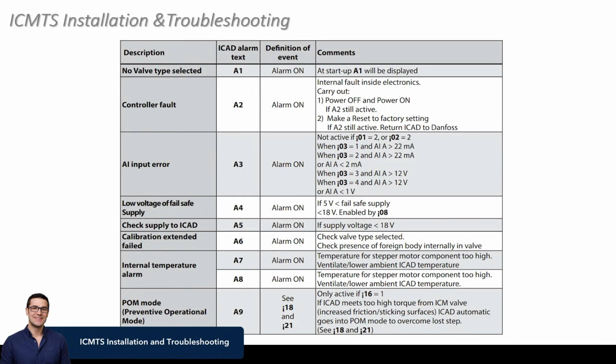But you can get an alarm code there that, if you're having problems, you can check, and it would point you in the direction of what type of alarm it is. Typically some sort of signal that we're not getting that we think we should. And so, yeah, you can use this as a troubleshooting guide as well.